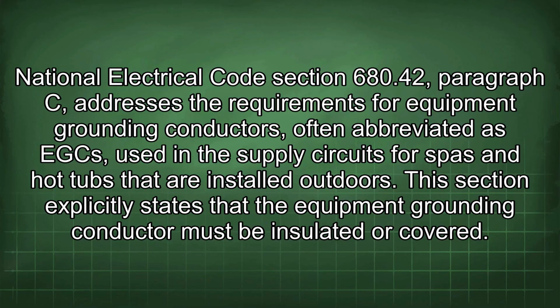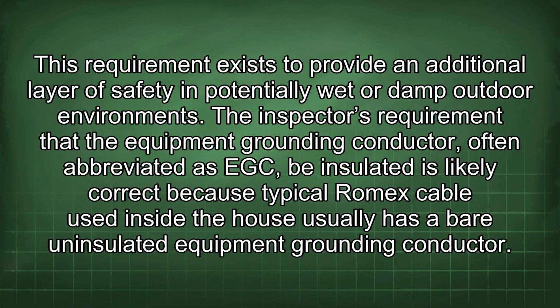National Electrical Code Section 680.42, paragraph C, addresses the requirements for equipment grounding conductors, often abbreviated as EGC, used in the supply circuits for spas and hot tubs that are installed outdoors. This section explicitly states that the equipment grounding conductor must be insulated or covered. This requirement exists to provide an additional layer of safety in potentially wet or damp outdoor environments.